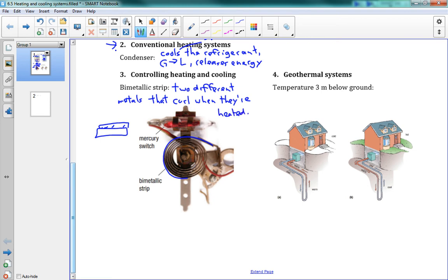They curl when heated because they're expanding and contracting at different rates. This causes the whole system to rotate, moving an arm in a certain direction. That arm connects to what's called a mercury switch. The mercury switch contains liquid mercury, which conducts electricity. When it's at a certain level, the mercury connects two contacts, completing a circuit. But as the strip curls and tips, the mercury shifts to one end and no longer connects the contacts, turning the switch off.